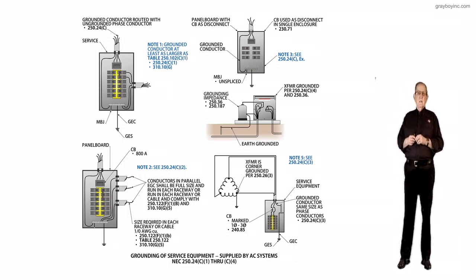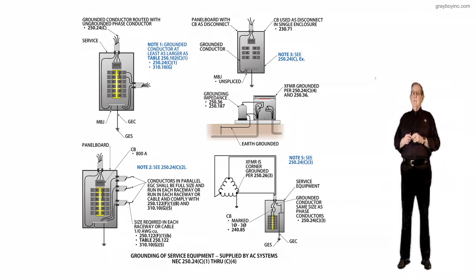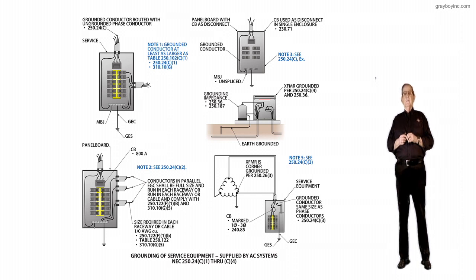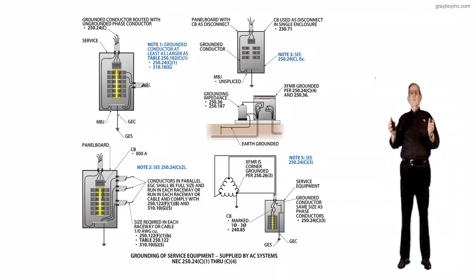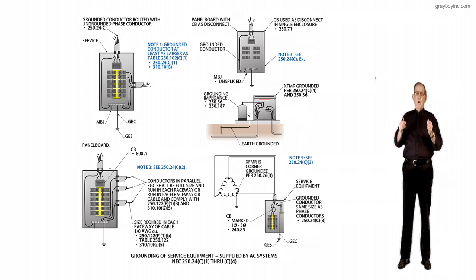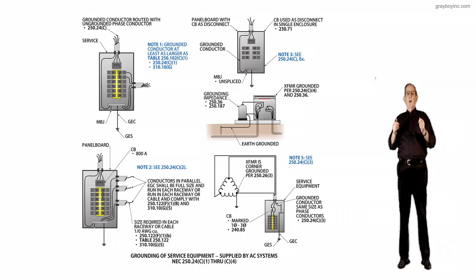And we know the 1/0 rule, that the neutral has to be at least 1/0 no matter how it calculates, and that's because of the resistance of the smaller conductors. You just wouldn't get the full amount of amps that you needed for a parallel hookup. And now I would like to remind you that to understand this, you would need to look at 250.24(A)(4), 250.24(B), and 250.28. Also look at 250.122(F), look at 310.10(H) and (G), and this comes together for you so that you really understand it clearly.